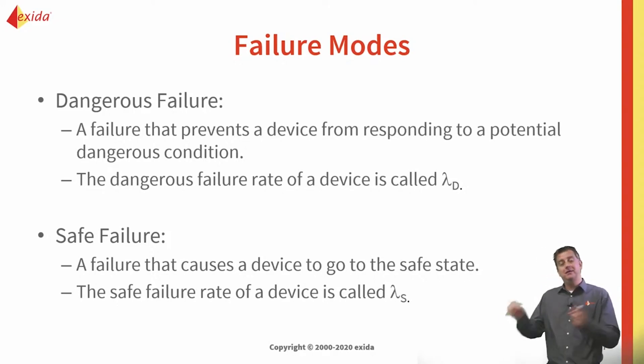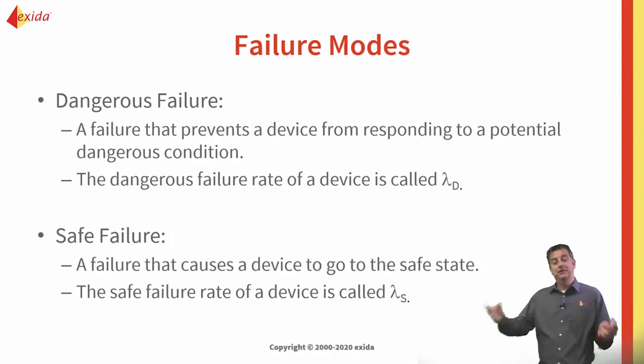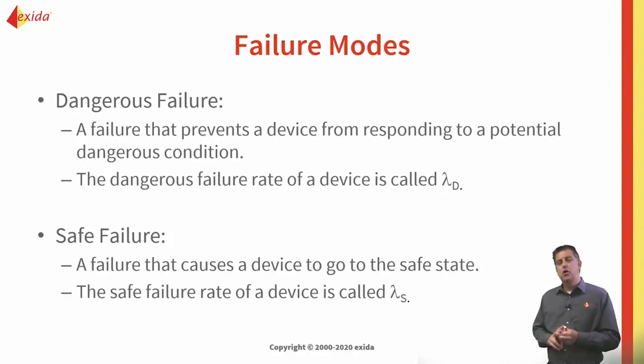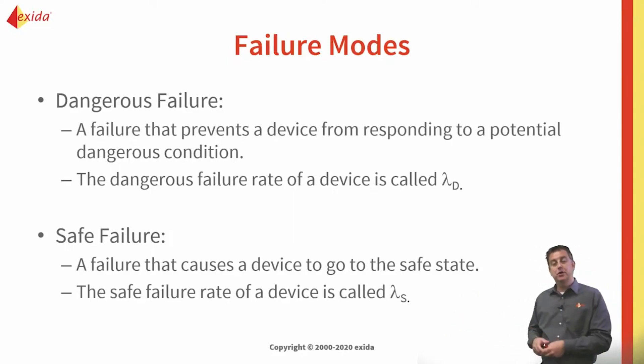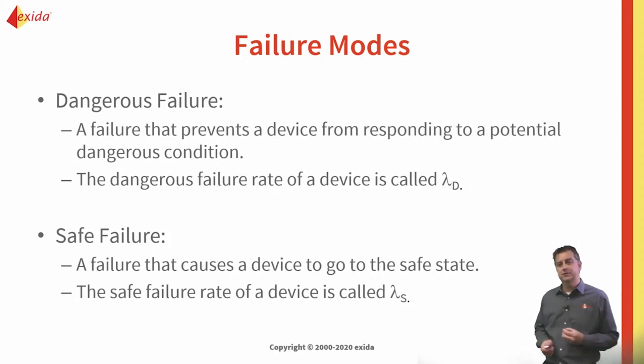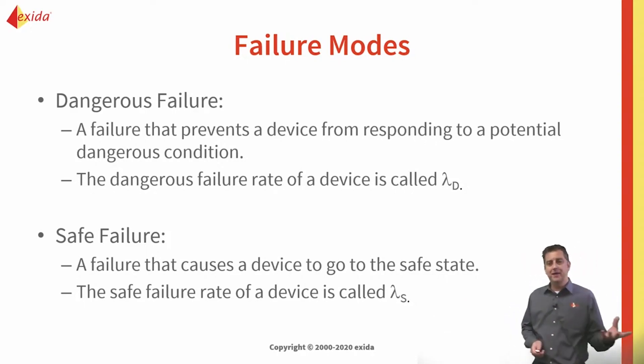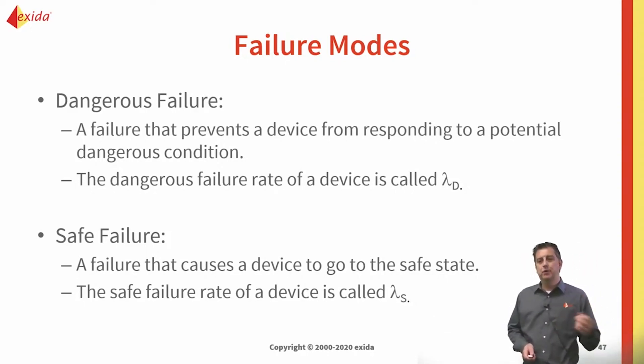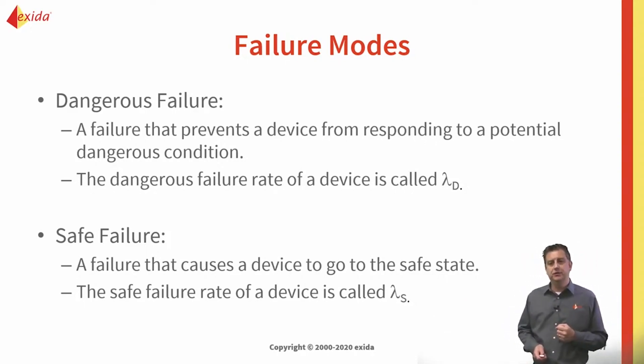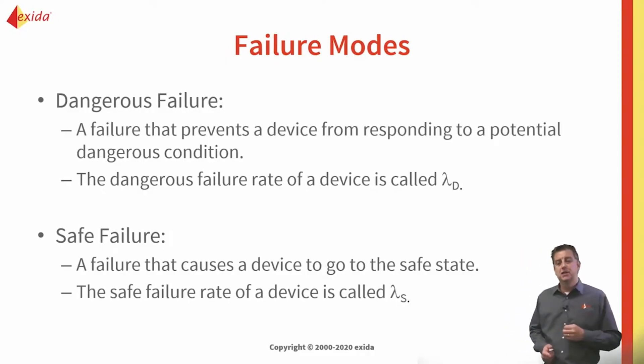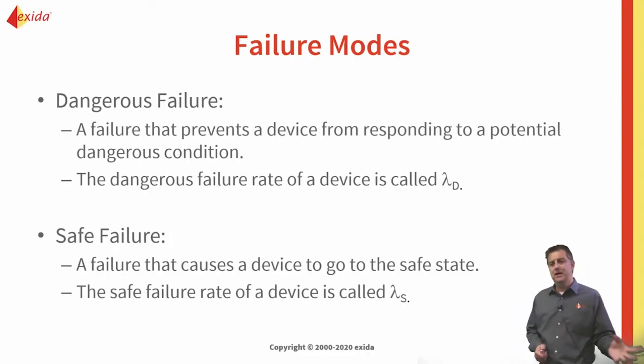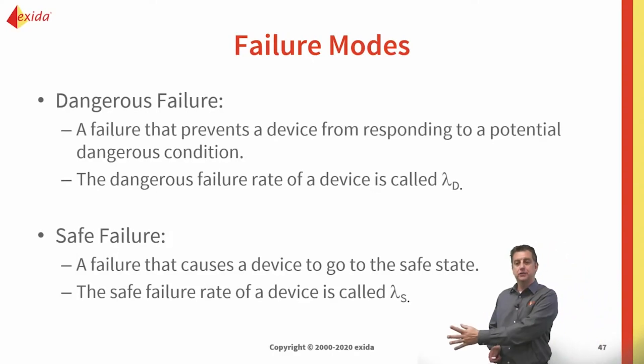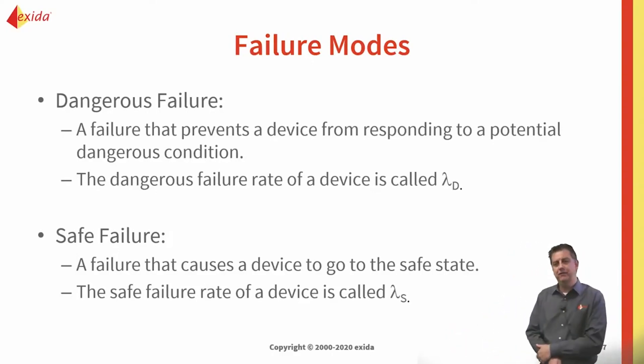Does the safety function prevent me from going to a safe state — does it fail dangerously? Or does the safety function cause a spurious trip, causing a transition to the safe state when there is no demand from the process? A failure that prevents a device from responding to a potential hazardous condition is a dangerous failure; a failure that causes the device to go to the safe state is referred to as a safe failure.